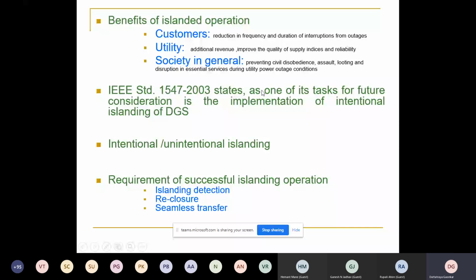Somebody may ask you a question. You may have a photovoltaic system. When power goes, why can't you operate it? That is because of security concerns, and you are not allowed. But in future, as per the standard, you will be required to operate. In order to do that, your inverter must have the capability. So grid inverter capability should be there.